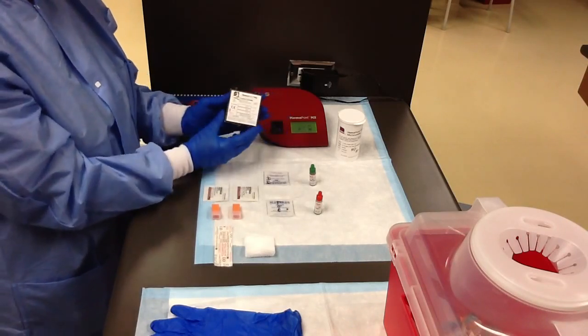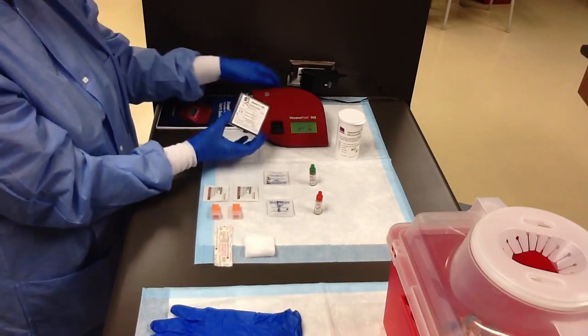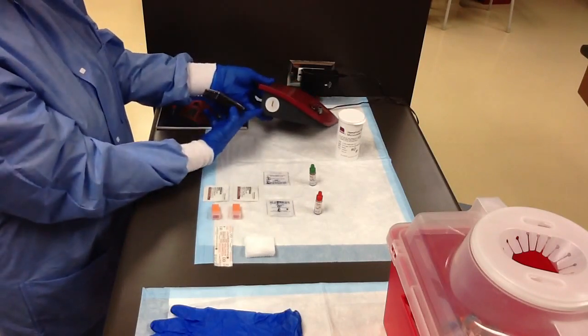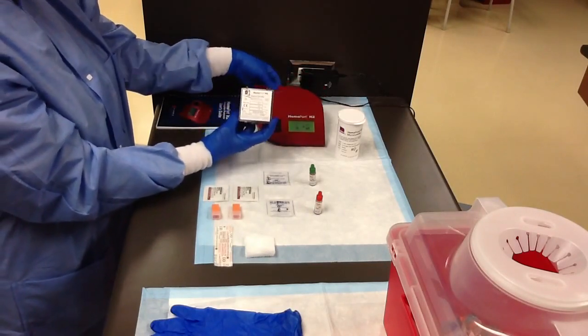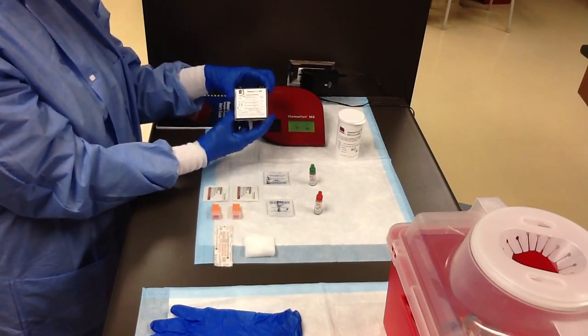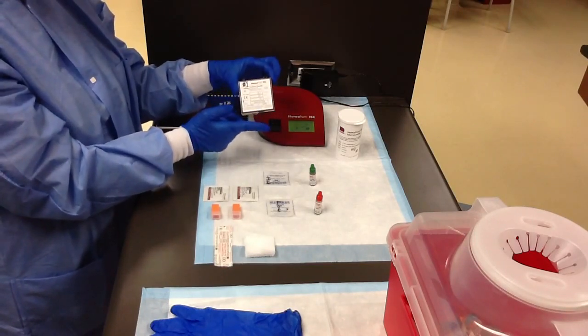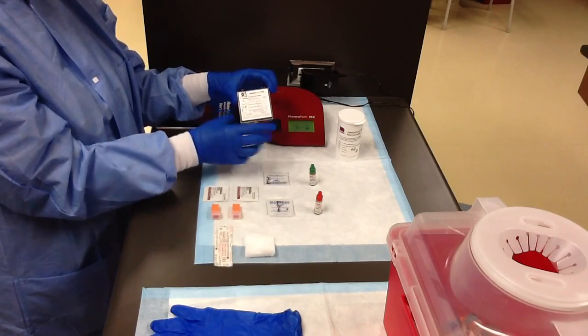Also, please note that the cuvette is numbered, as is the machine. It's very important that you match the control cuvette to the machine. Do not lose this cuvette. Do not accidentally throw it away.